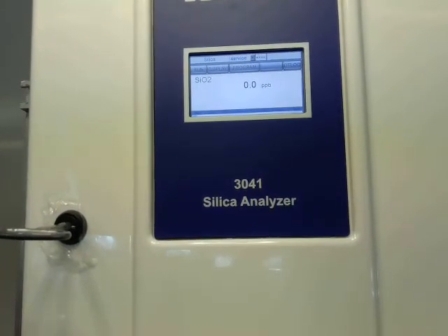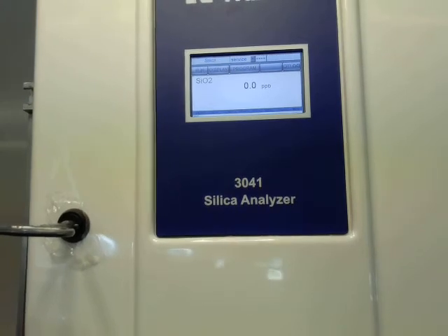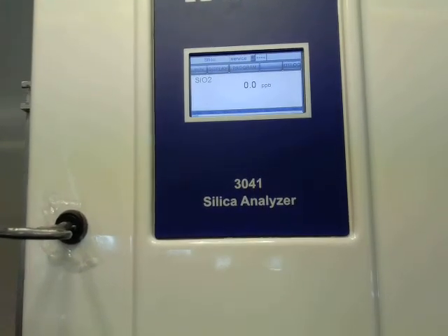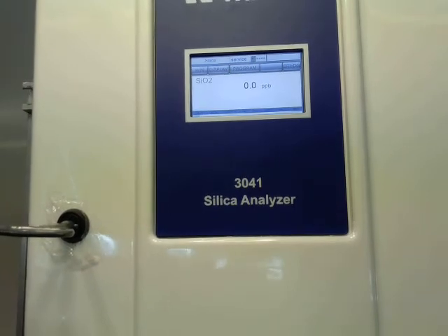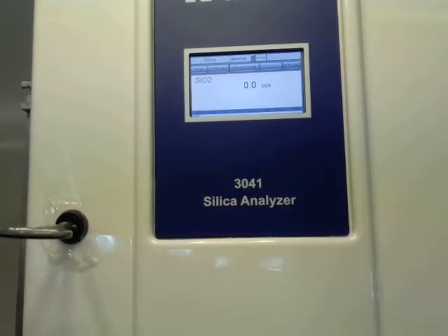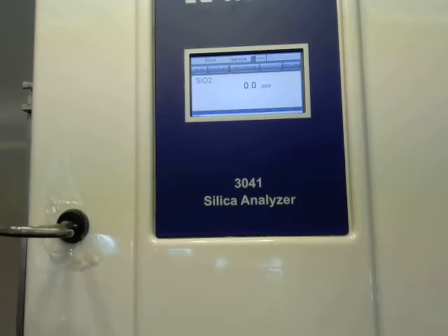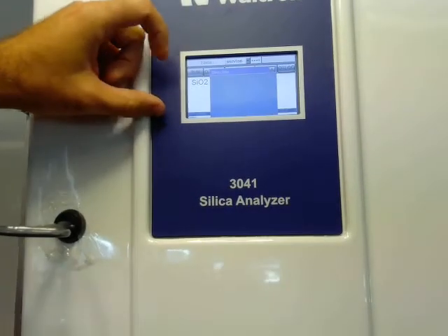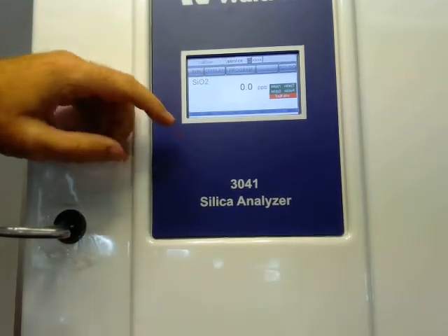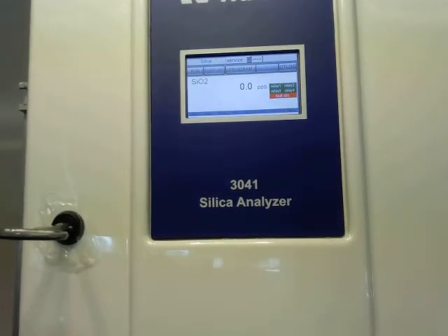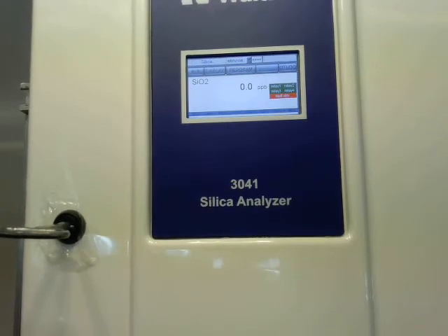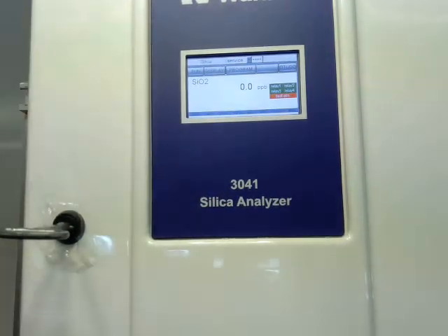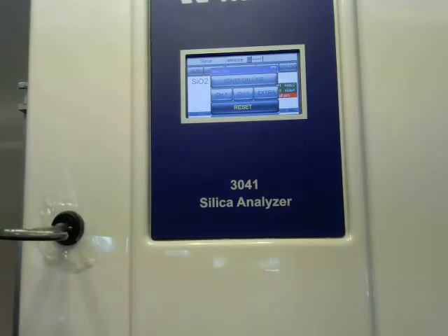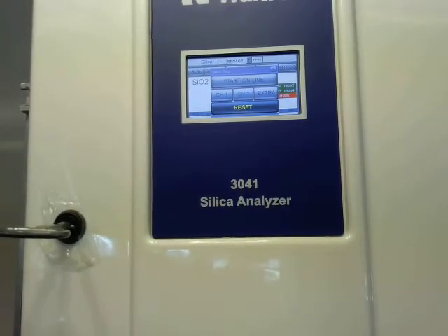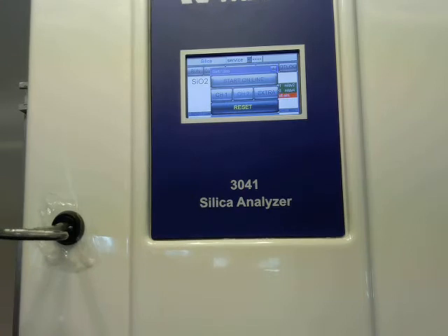So if we were getting ready to do a reagent replacement or something like that, or maintenance, we would let it finish, and then we could go ahead and take the analyzer offline. If we didn't really care what the reading was right now, and we just said, hey, we're ready to do our maintenance, we could certainly come into the run menu and hit this emergency stop button. So that just stops the analyzer in whatever it's doing, mid-cycle. We do get an alarm that pops up for a fault, just saying, hey, you stopped the analyzer for some reason. And that way, if you had that alarm wired into your DCS or something like that, you get a notification that somebody stopped the analyzer and it's offline.